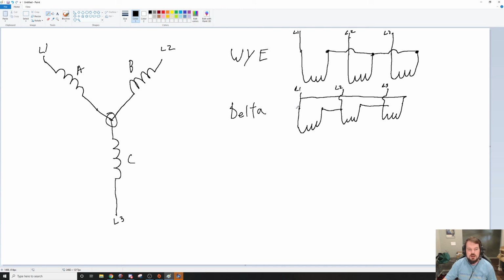More things about the Y. To identify them from the voltage, Y has weird voltage, like 208, 277, those sorts of things. If you take the lower voltage of a dual voltage transformer and double it and it's not the higher voltage, that's a Y transformer.